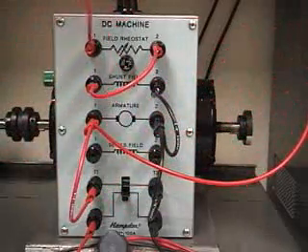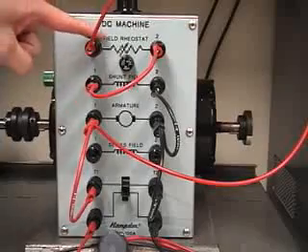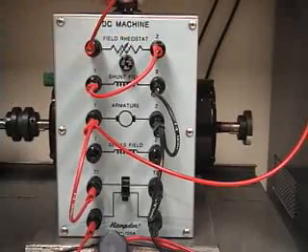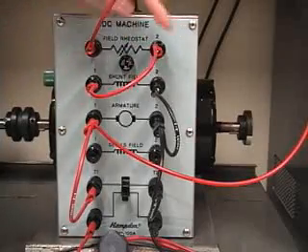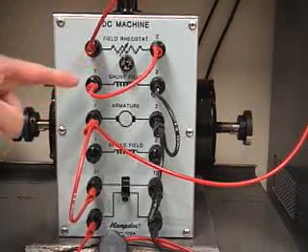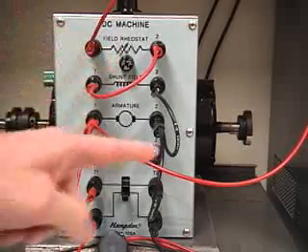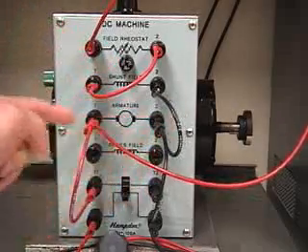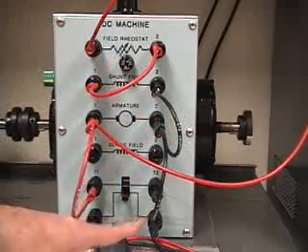Coming back from the ammeter to the field circuit where it's run through a field rheostat, a variable resistor adjusted on top here, and that is in series with the actual shunt field winding that's wound on the stator of the machine. Through the shunt field winding we complete the negative circuit path to the armature and back to the source.